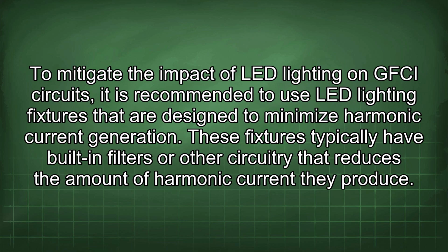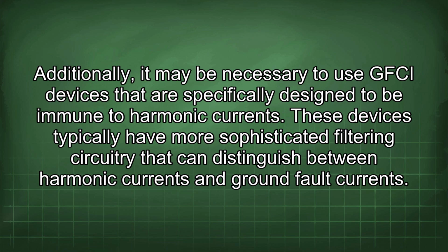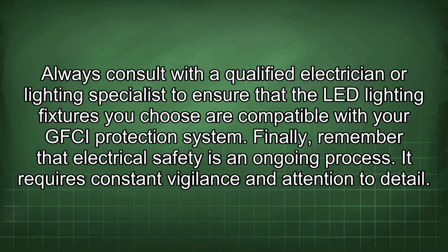To mitigate the impact of LED lighting on GFCI circuits, it is recommended to use LED lighting fixtures that are designed to minimize harmonic current generation. These fixtures typically have built-in filters or other circuitry that reduces the amount of harmonic current they produce. Additionally, it may be necessary to use GFCI devices that are specifically designed to be immune to harmonic currents. These devices typically have more sophisticated filtering circuitry that can distinguish between harmonic currents and ground fault currents. Always consult with a qualified electrician or lighting specialist to ensure that the LED lighting fixtures you choose are compatible with your GFCI protection system.